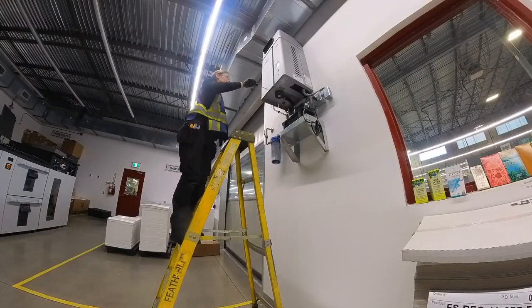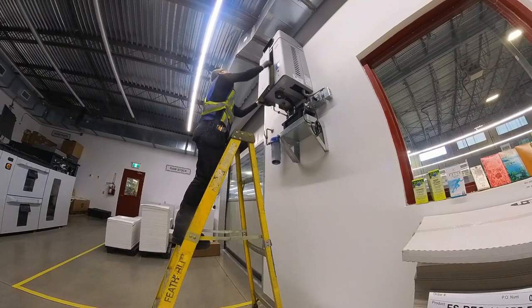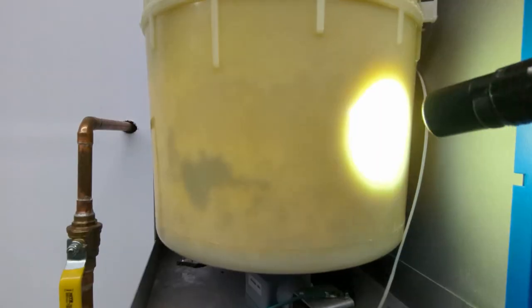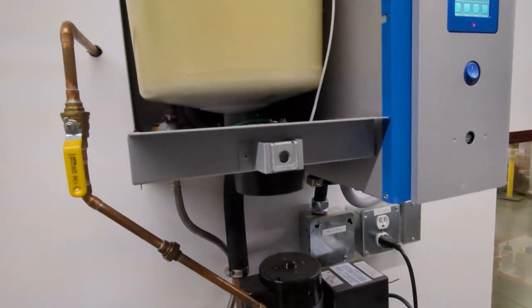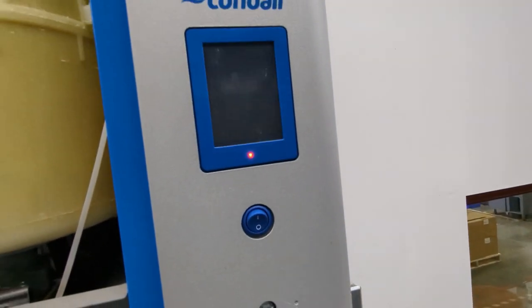Now it's my turn — I get to change my humidifier pot, the exact same thing that Trevor did on his. Step one is to always make sure that the humidifier pot is empty before you start doing anything. There's scalding hot water inside there, and if you disconnect everything it could all land on you. So empty the pot and then turn the unit off.